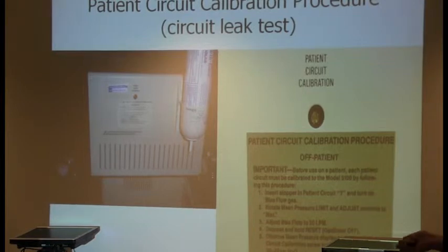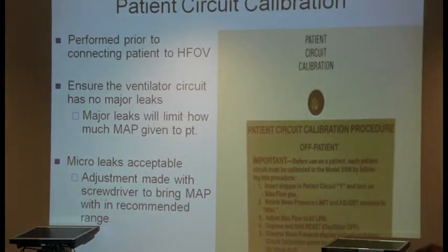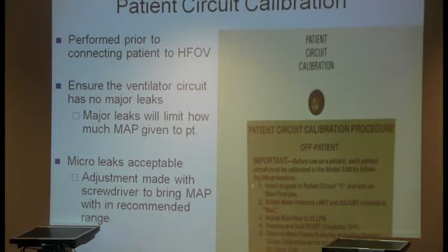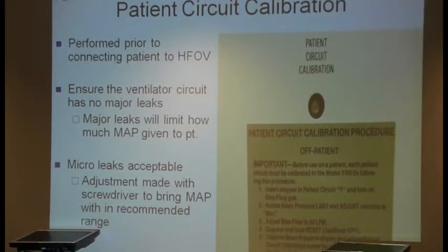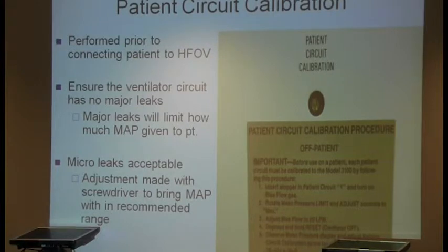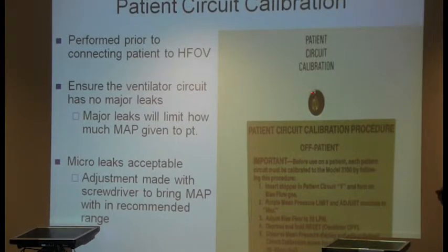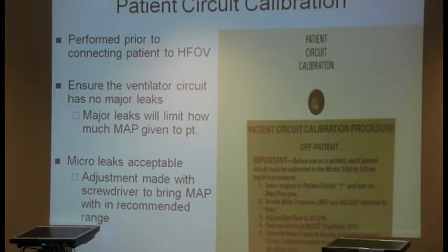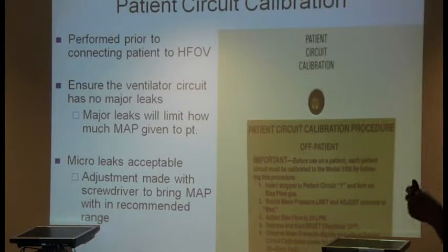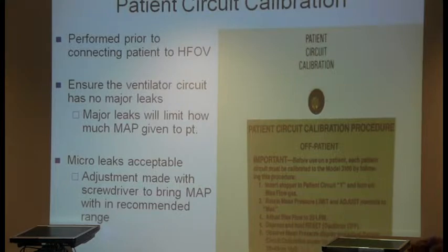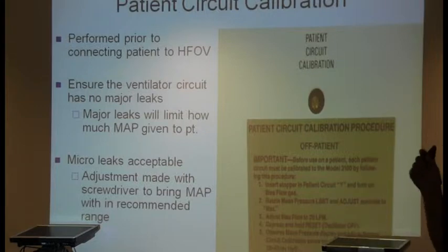No major leaks. Now, micro leaks are okay. You're going to have small leaks, that's okay, but you'll be close. So if I do this test and I get a different setting, say a 36 or 35, you can come up here and adjust the screw, but you're cheating, because what the screw is meant for is the micro leaks. So if my number says 37, 38, and I need to be 39, then I can come over here and turn this dial to 39, get it within specs, because those are micro leaks.